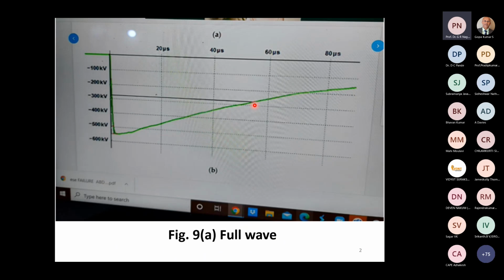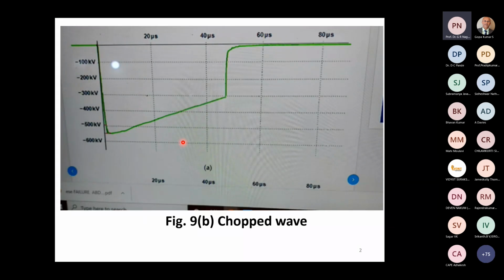Now let us take the case of a chopped wave, or a flashover occurring. If I apply this same voltage wave to a gap, you'll see it goes to the peak, comes down, and the gap may flash over somewhere here. This is what we call a chopped wave - it has flashed over, so the voltage comes down to 0 very rapidly. This is called a chopped wave. The time from 0 to the instant where the flashover starts is called the time to chop. So this voltage and this time to chop together form what we call the voltage-time characteristic.